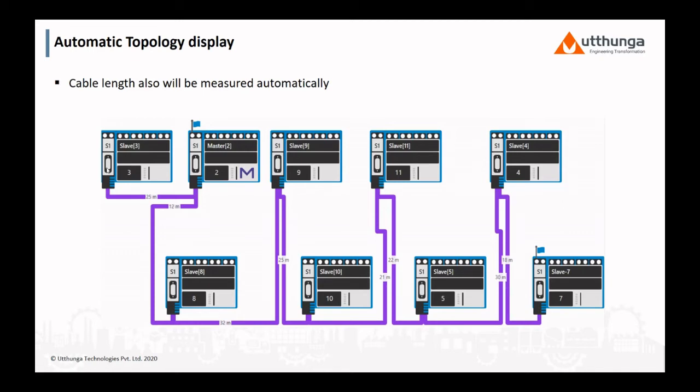With the PBQ1 device, as well as the integrated oscilloscope, you can identify the EMC, the signal shape, and the reflections. If the reflection is too high, we need to do the termination in the network, because without terminations the reflection is too high, and that may cause problems in your PROFIBUS network. That is why you can also identify and measure this reflection report through the PBQ1 device.